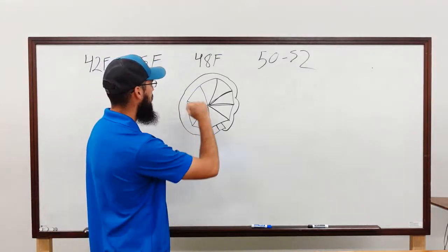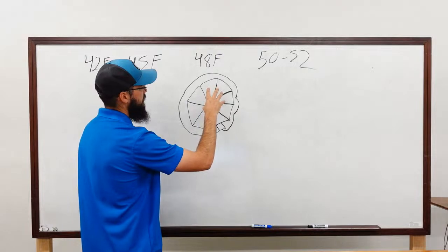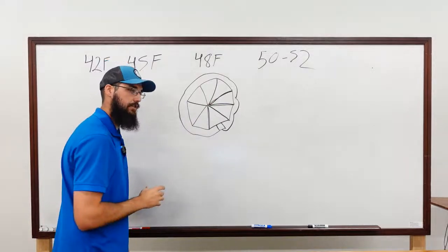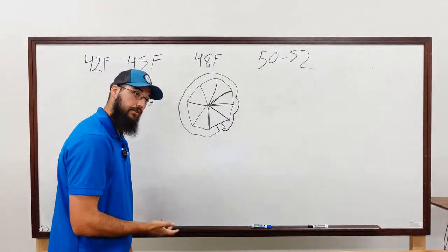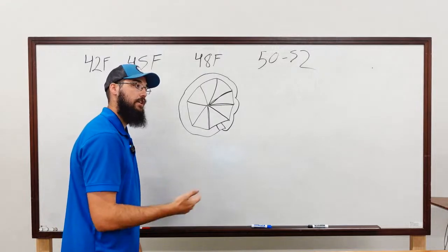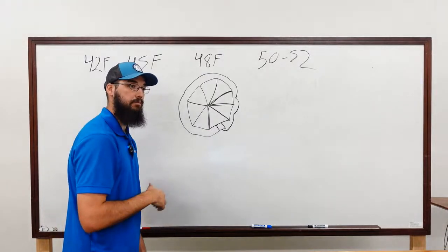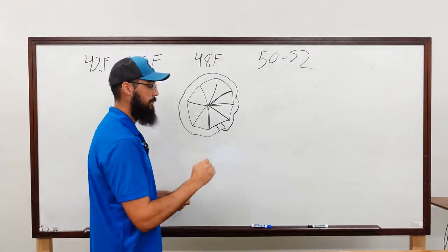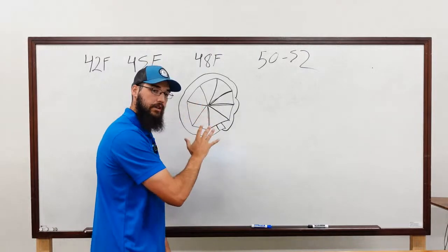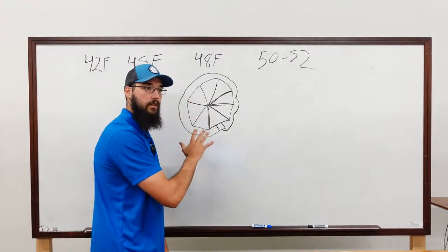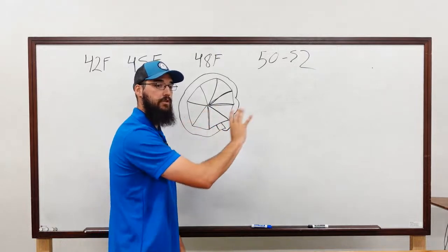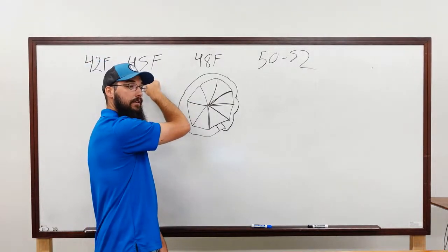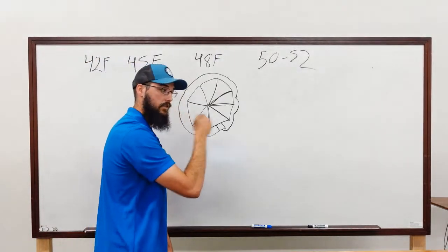Anyway, so a current limit. Current limit is another thing that's going to restrict how much these vanes are allowed to open. Another thing would be a suction limit or low suction pressure limit. So if for any reason your suction pressure is too low, it's not going to let this continue to load the machine. It's going to stop it. Even though you're under the current limit, even though you still haven't made set point and you're still trying to pull down, that suction pressure will stop you.